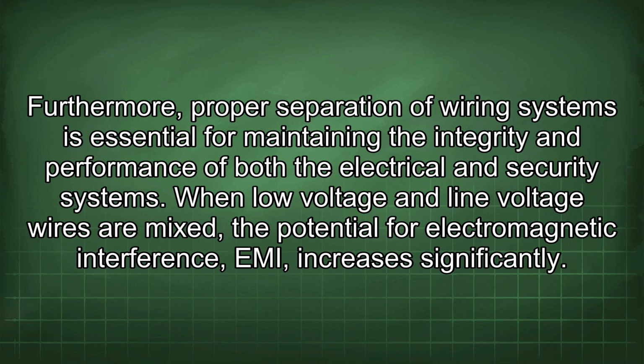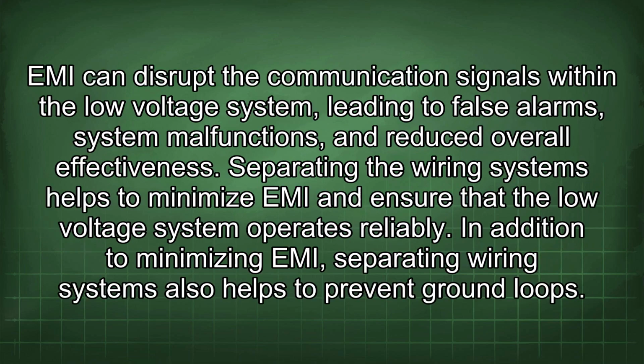Furthermore, proper separation of wiring systems is essential for maintaining the integrity and performance of both the electrical and security systems. When low voltage and line voltage wires are mixed, the potential for electromagnetic interference (EMI) increases significantly. EMI can disrupt the communication signals within the low voltage system, leading to false alarms, system malfunctions, and reduced overall effectiveness. Separating the wiring systems helps to minimize EMI and ensure that the low voltage system operates reliably.